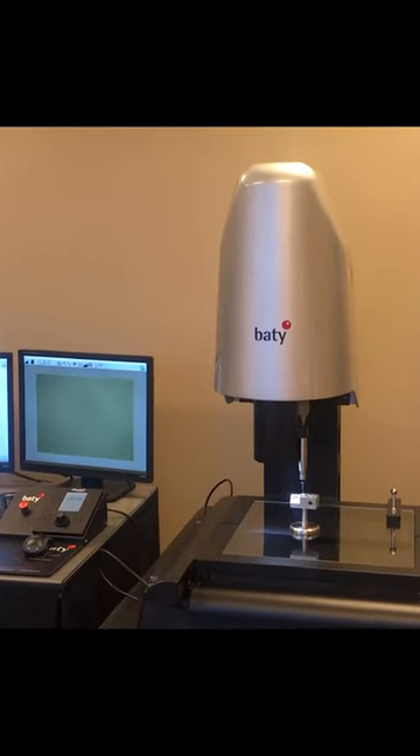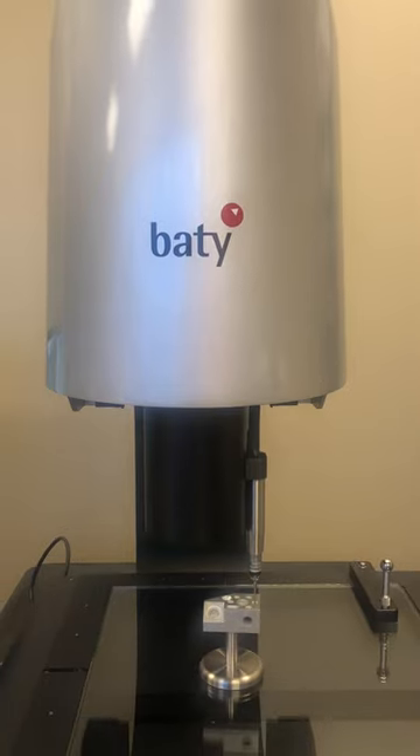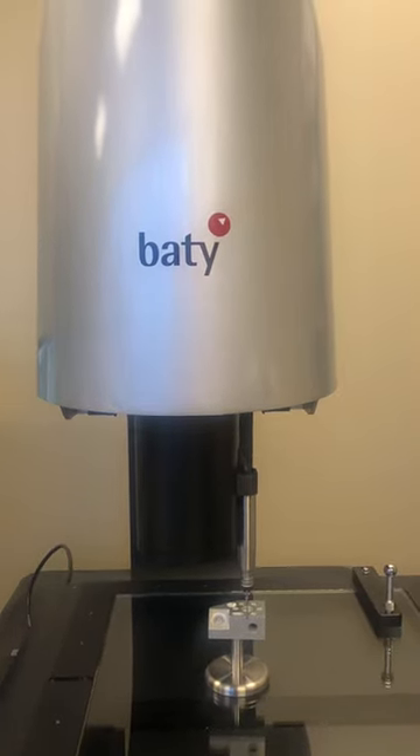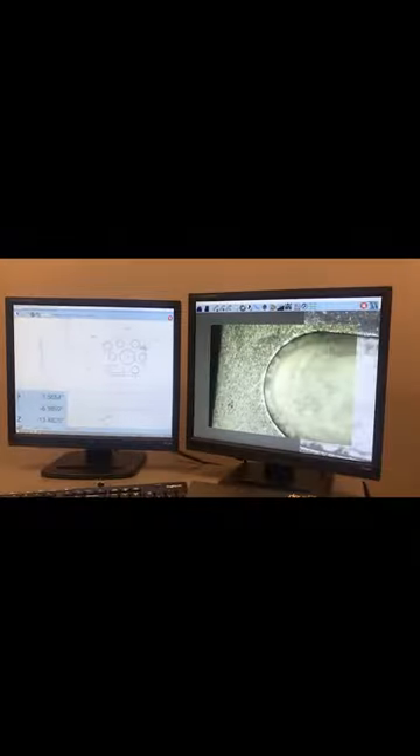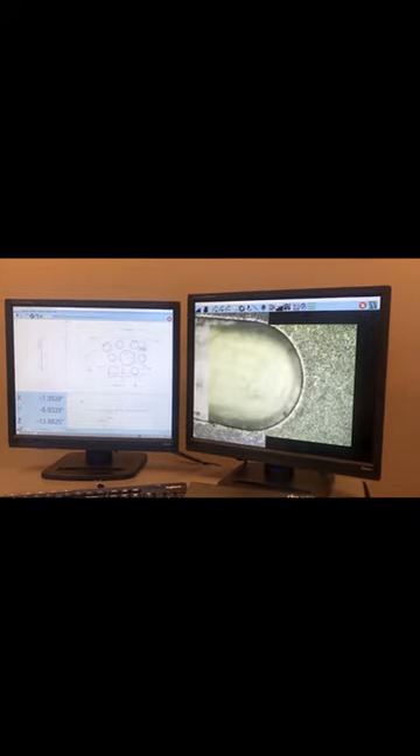The Baty system utilizes the Renishaw TP20 touch probe system. There are many different probing configurations that we can utilize. The optics of the system are a 6.5 to 1 ratio zoom, and we can change the magnification very quickly and very easily.